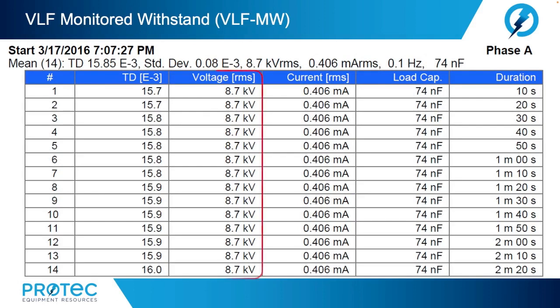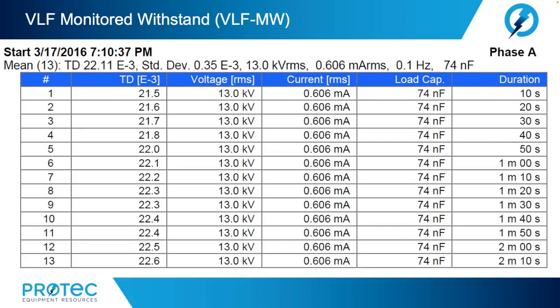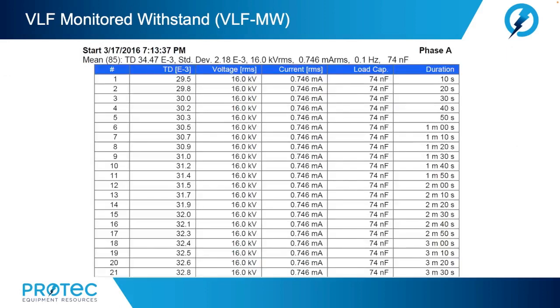Now, at a voltage level of 8.7 kV, 1 times U0 phase to ground, we now see that the standard deviation has gone up to 0.08, still well within the parameters specified in the tables of merit provided in the IEEE document. When we reached a voltage of 13 kV, which was 1.5 times U0, we now see that the standard deviation has grown to 0.35. And finally, when we get to our withstand voltage, we now see at 16 kV, the standard deviation has jumped to 2.18, well outside of the parameters of the tables of merit.